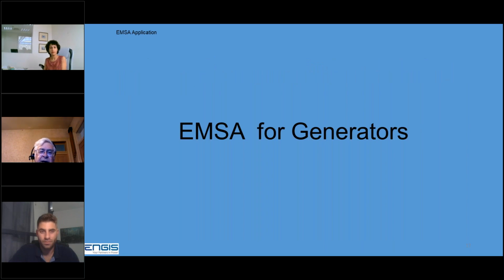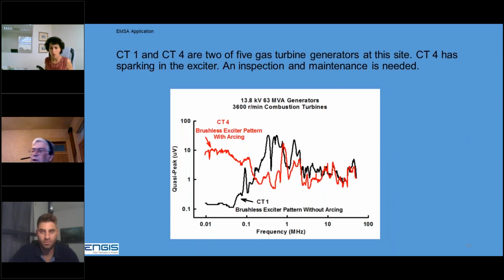EMSA is applied for generators. This particular site has 5 gas turbine generators. What I'm showing here is CT1 and CT4. CT1 brushless exciter, the black curve is there. Very low readings with the brushless exciter on CT1. The brushless exciter on combustion turbine 4 is much higher, and it has arcing.